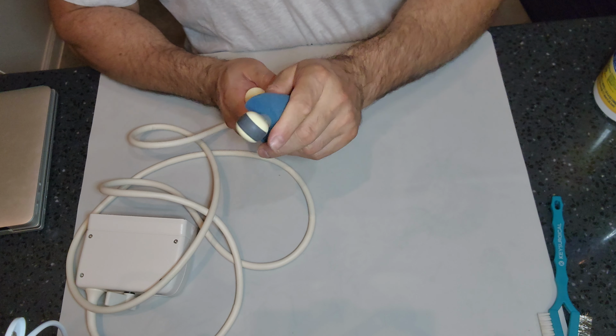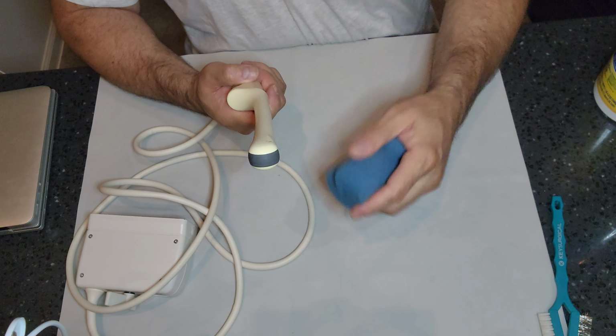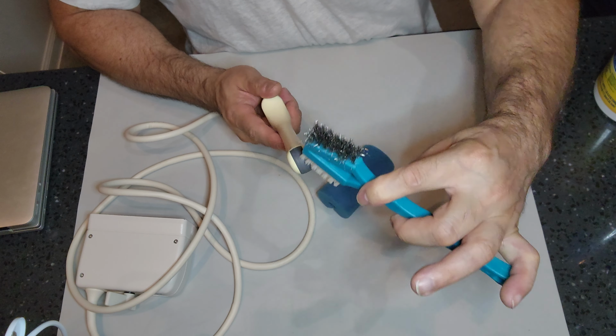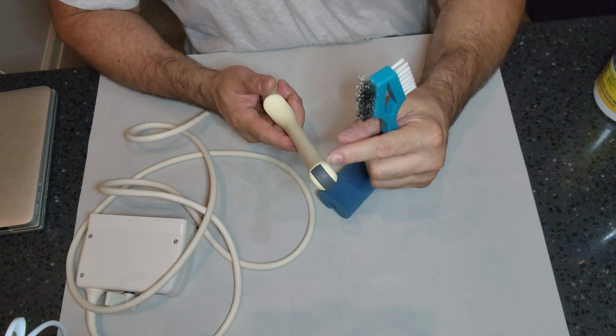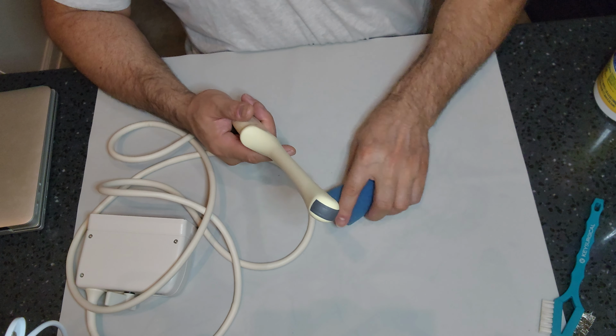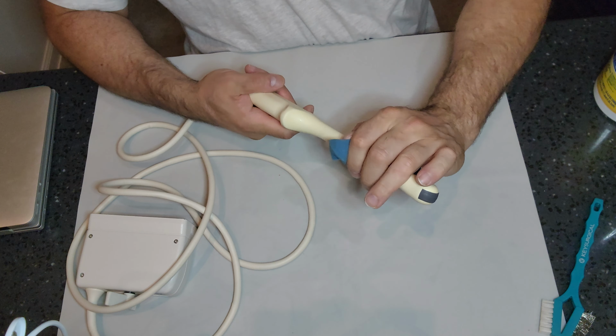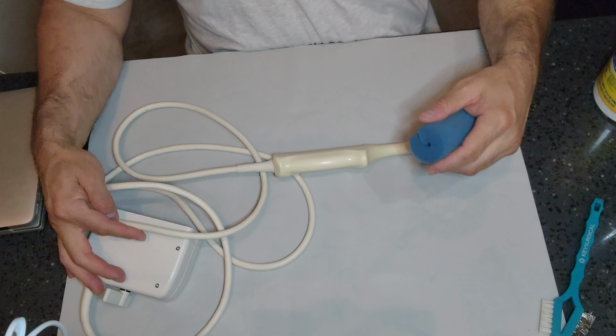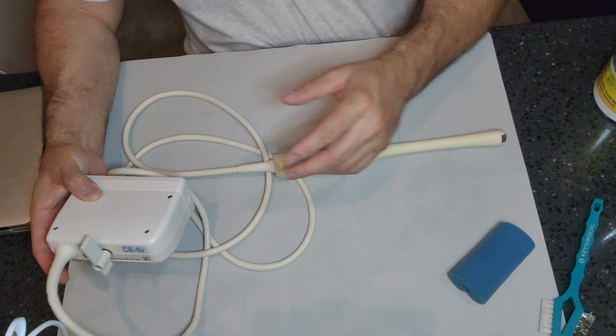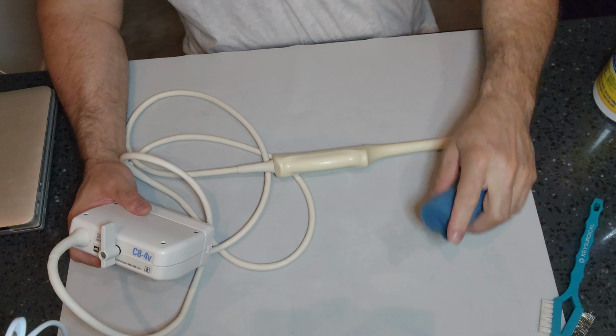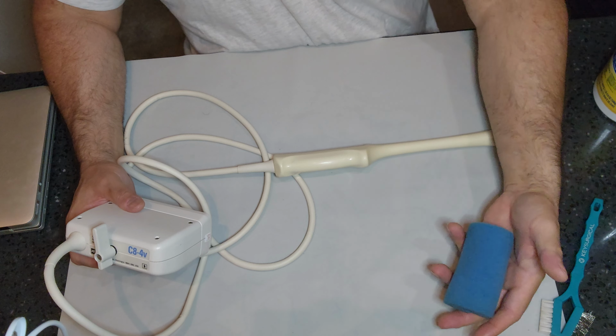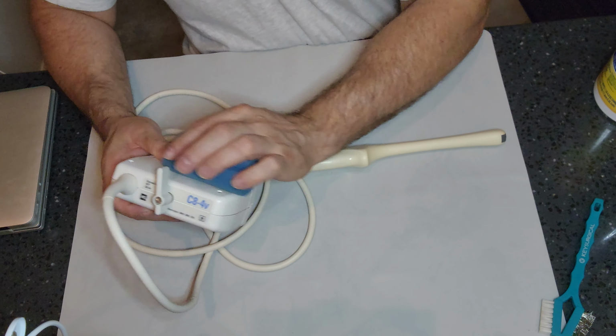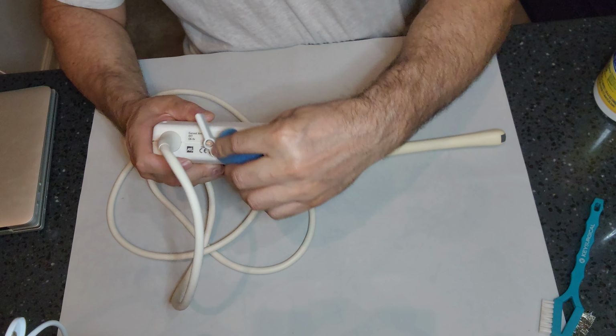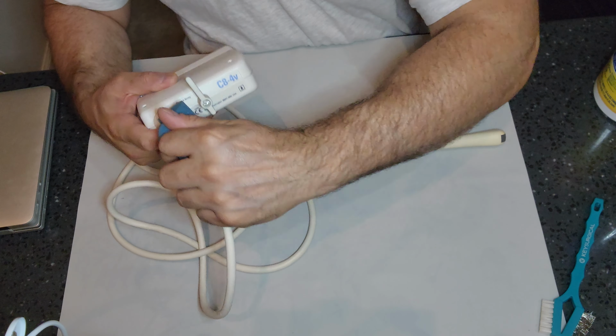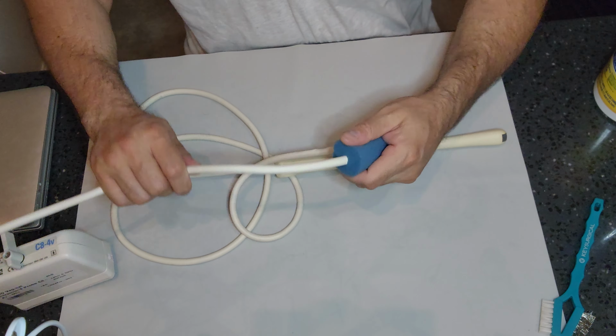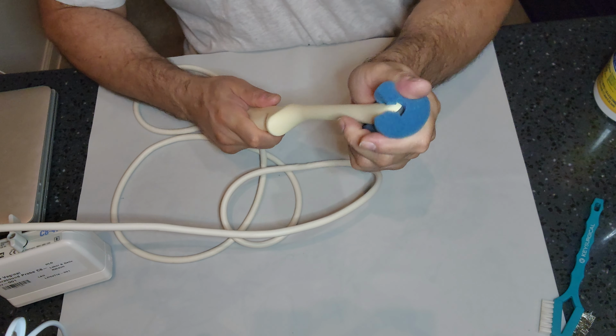And again, refer to those IFUs, the distal tip or the working end of the instrument. Can you use a brush on it? Many IFUs state not to do it because scratching that lens or that rubber piece interferes with the device and it can malfunction. So a soft brush or sponge to clean with your detergent. Next, you want to rinse, okay? So again, best practice is treated water. Again, refer to that IFU. You're not going to be spraying your instrumentation with water. You're going to be using a new sponge or a new towel with treated water, and you're going to wipe off the exterior. Again, making sure that the connector's facing down. A good wipe down around to get rid of that detergent or that cleaner. Wipe down all the way down to the control body as well, making sure you're getting all that detergent off of it.